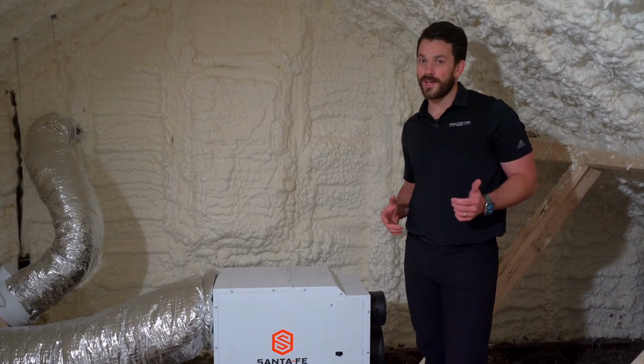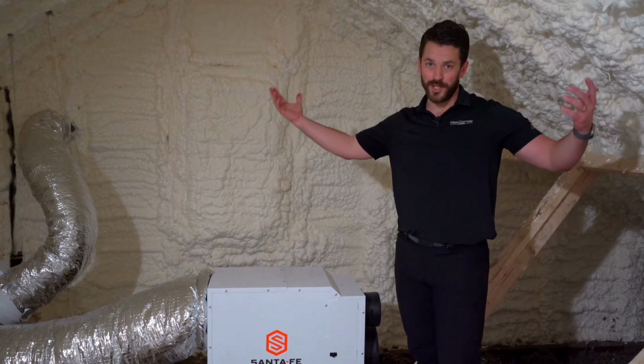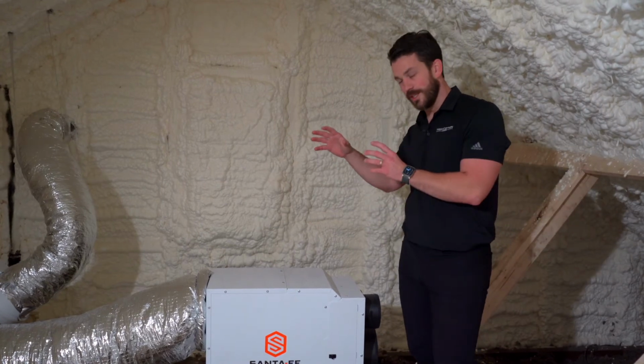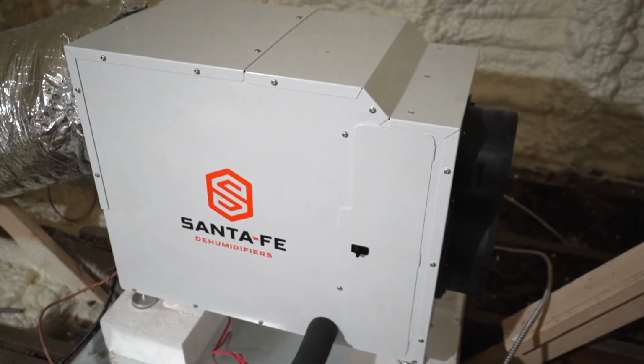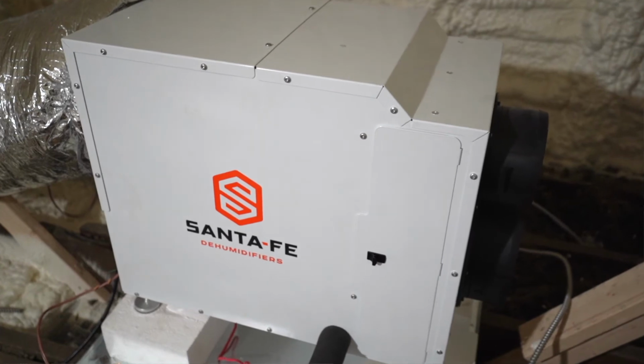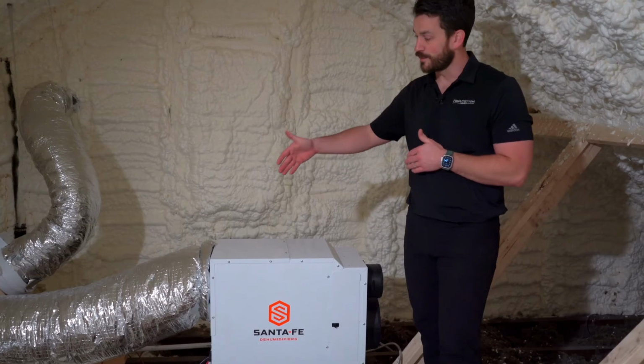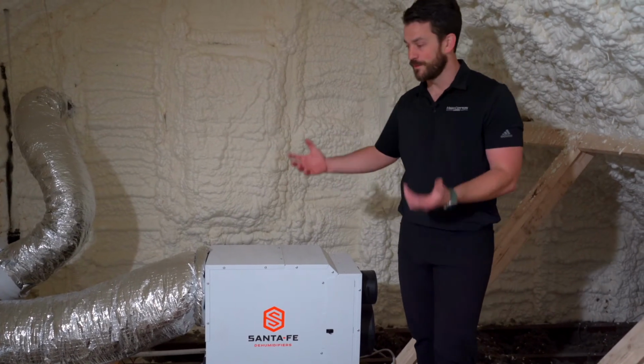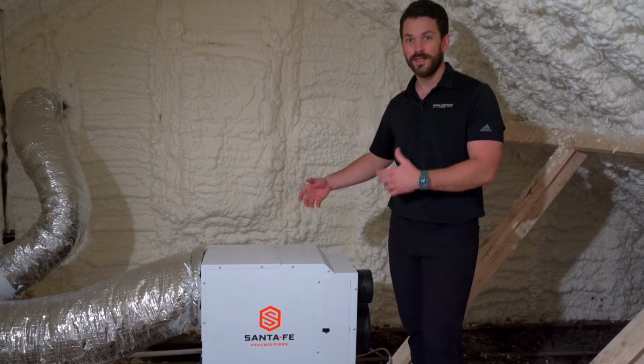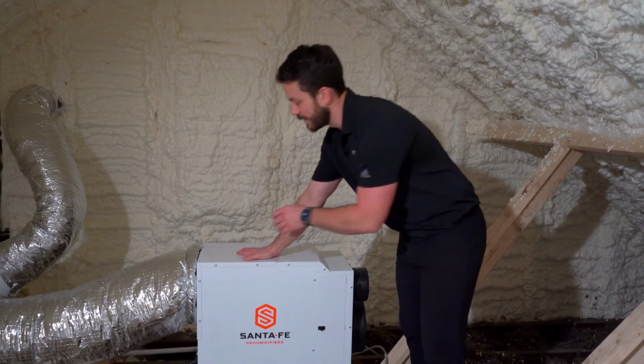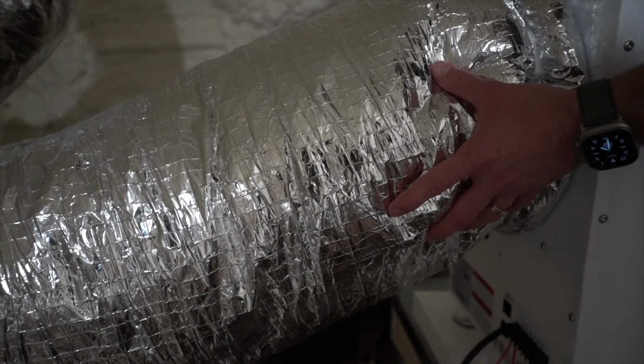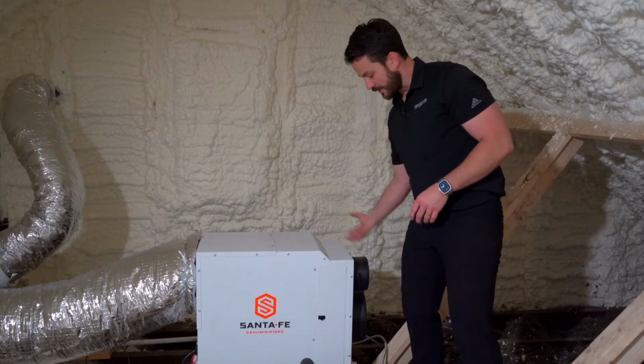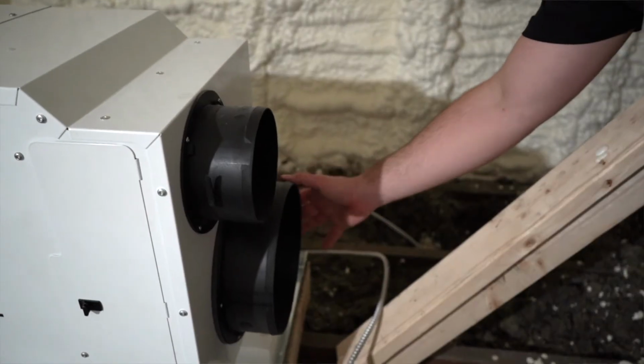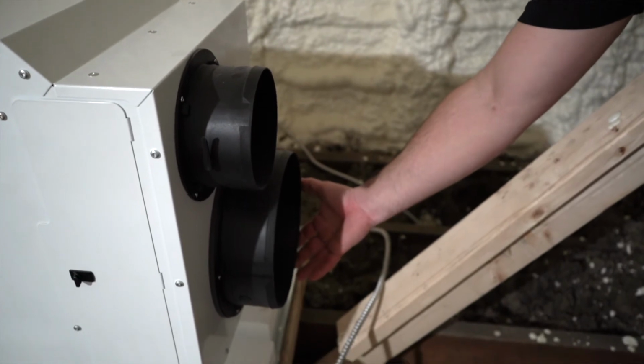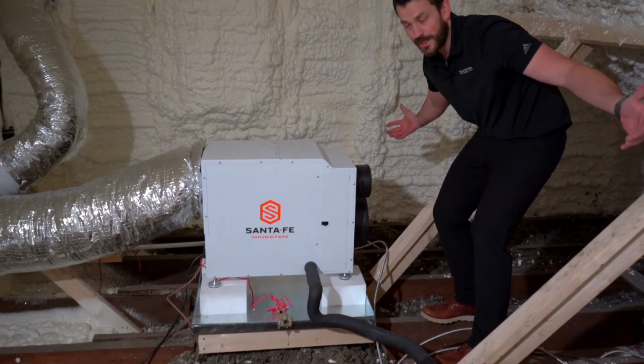We're in the attic now, and you can see open cell foam all over my head. In front of me is the Santa Fe 120H dehumidifier. You can tell by looking at it that this is the supply duct coming off the back—if you're familiar with these installations, it's no surprise. This is the supply side, going out to one of the rooms below. The return side is over here, with this bigger pipe being the return, just sucking air from the attic we're standing in.